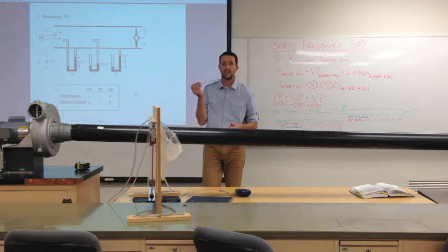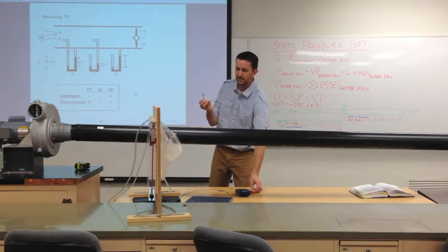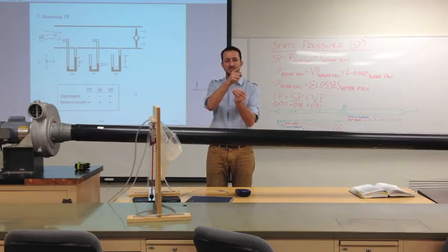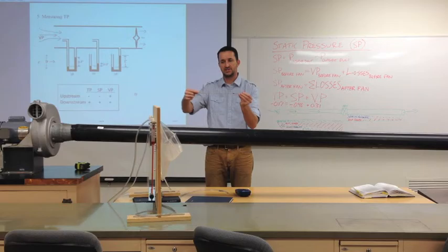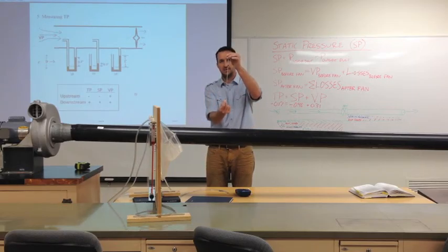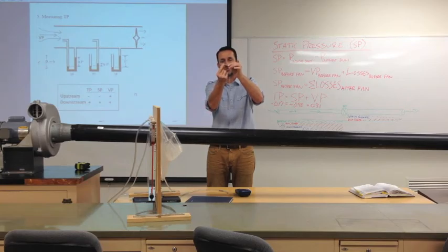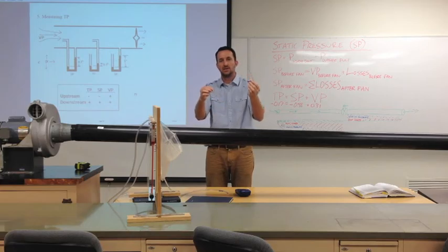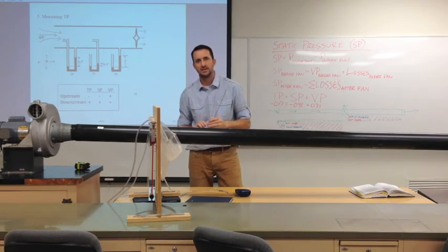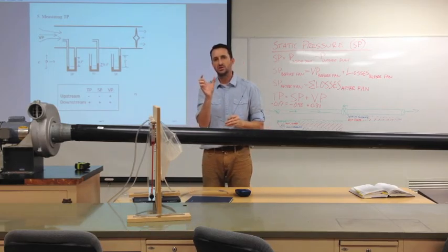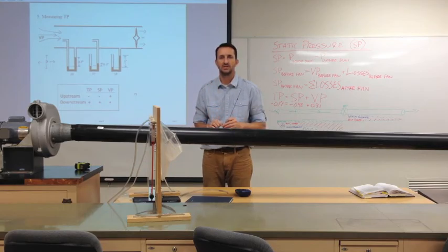Okay. We also kind of covered the use of the pitot tube. The velocity comes in this hole right here and out this section there. The static pressure goes in these holes in the sidewall of the pitot tube and comes out this side here. By hooking those up to a manometer, you can measure that inches of water gauge to quantify all of these for ventilation purposes. Hopefully that helps clear things up.